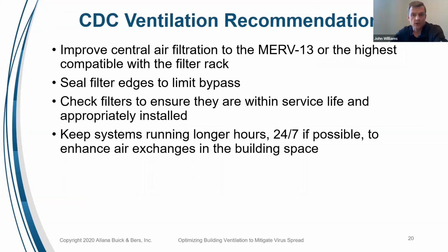The CDC also says to make sure we're checking our filters and installing the highest MERV rating filters possible. Now, this is going to really depend on what our filter racks are set up for, what they can accept, and more importantly, what our fan horsepower is able to do. If we install too high of a MERV rating in our systems, it's actually going to be counterproductive, and it's going to reduce our airflow in the system. And it's going to reduce the ventilation in the building.